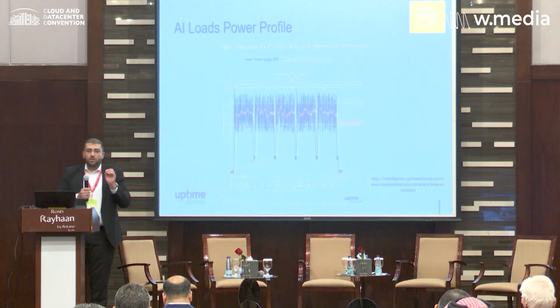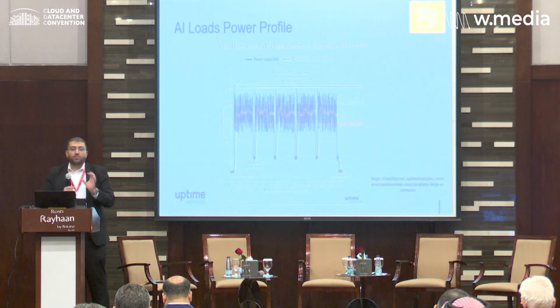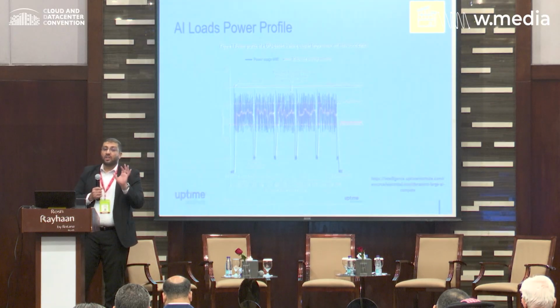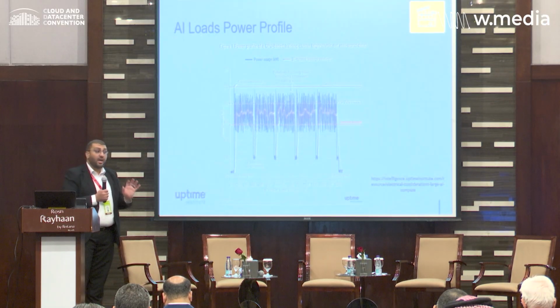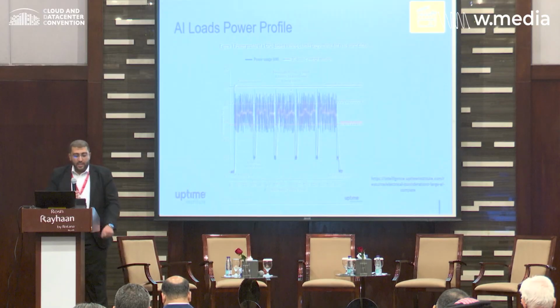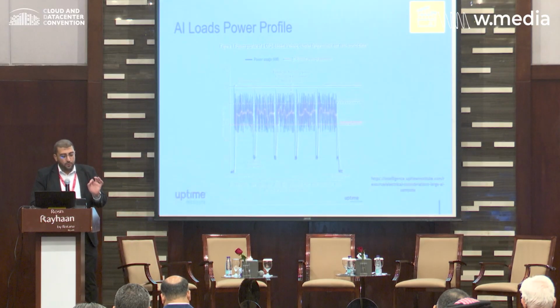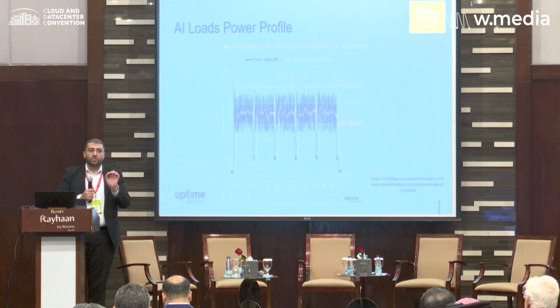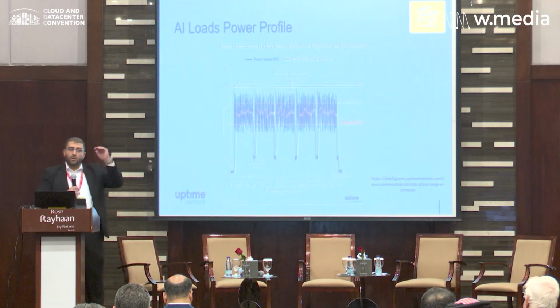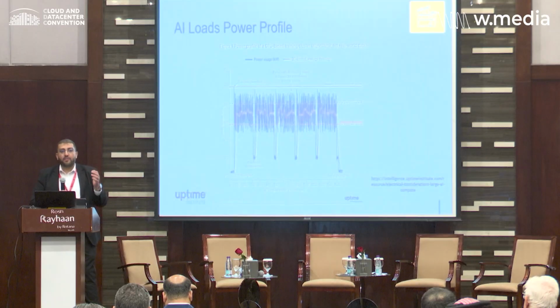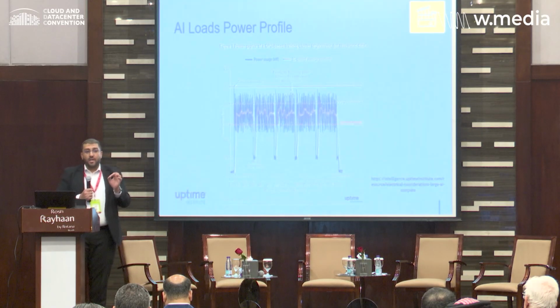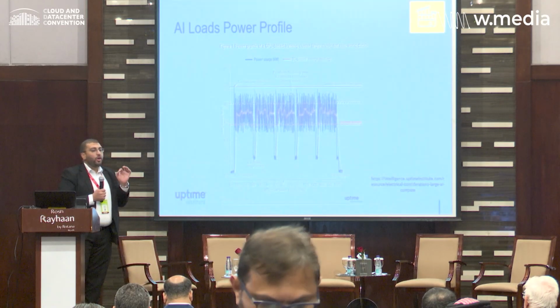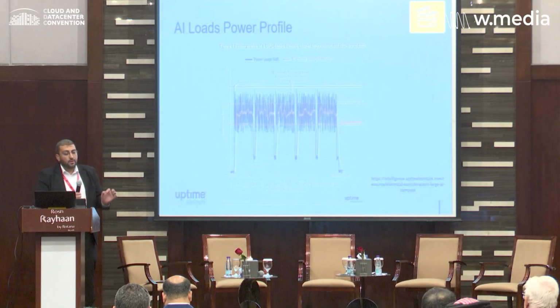This will cause challenges for the UPS because the current UPS, the traditional data center UPS, cannot handle such transients, as well as the engine generators. So the key here is to absorb and filter those fluctuations at the UPS level, to prevent those transients from propagating to the engine generators, to protect the engine generators, as well as to make sure there is no impact on the grid stability.